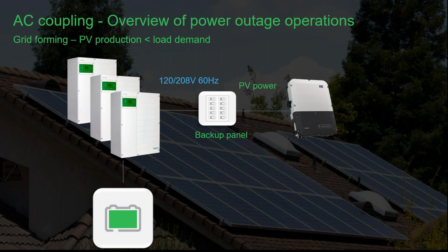In a backup scenario or a power outage, XW Pro forms the grid voltage and frequency, allowing the PV inverter to produce power. If the loads require more power than the PV can supply, the remainder will come from the battery. If the PV power exceeds the load demand, the excess will charge the battery until full, after which time the frequency shift algorithm will curtail PV production to protect the battery from being overcharged.